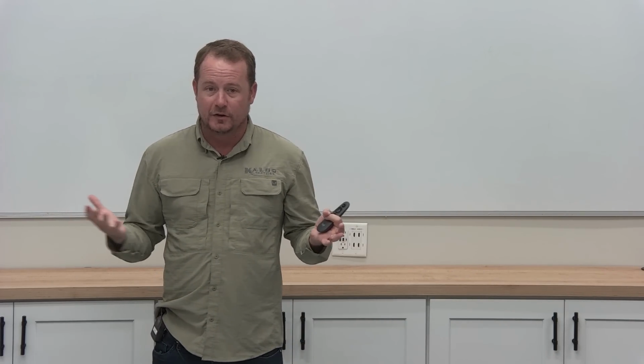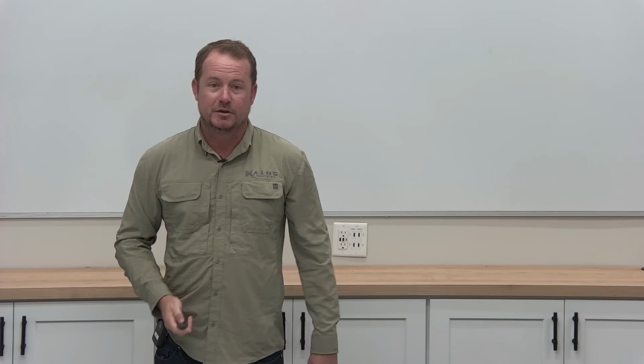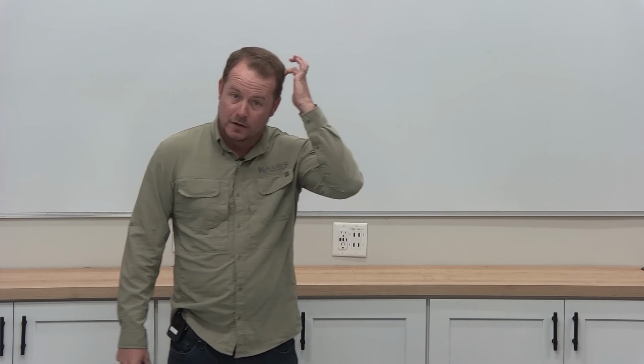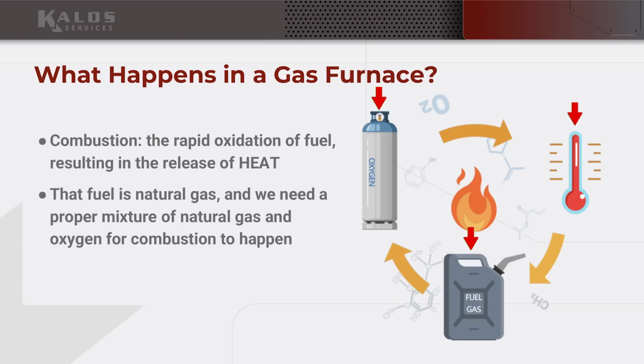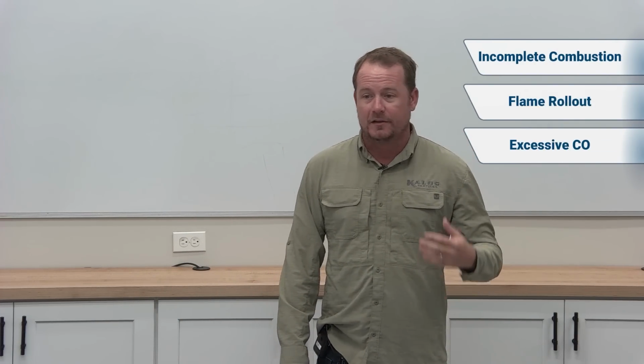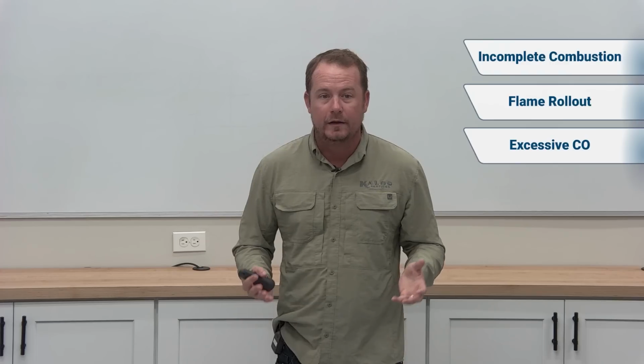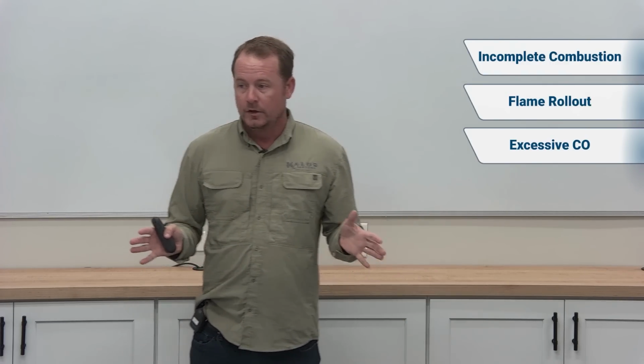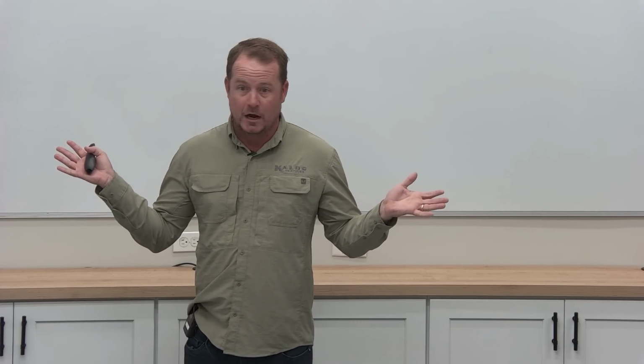Just think about it. What do we need for combustion? Air, fuel, and heat, right? It's the fire triangle. So if you have the fuel and you have the heat, but you don't have the air, specifically the oxygen in the air, what do you have? You have a really unsafe burning condition, and that's when you get incomplete combustion, that's when you can get flame rollout, that's when you get excessive carbon monoxide. All of these really bad things we don't want occur because you don't have enough oxygen. So every time we're working on any gas-fired appliance, we should be paying attention to where the oxygen is coming from.